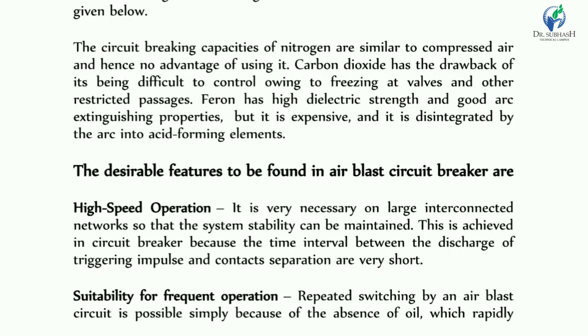Carbon dioxide is a drawback as it is very difficult to control. The freezing valve and other restricted parts tend to freeze. Carbon dioxide has high dielectric strength and good arc quenching properties, but it is expensive. Additionally, it is disintegrated by the arc into acid-forming elements, which is a significant disadvantage.